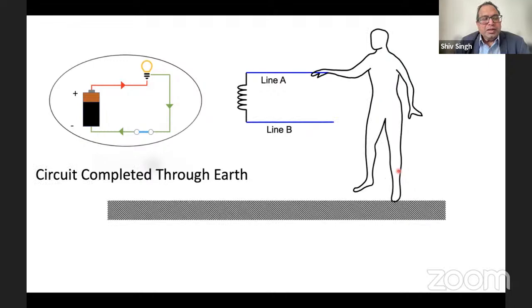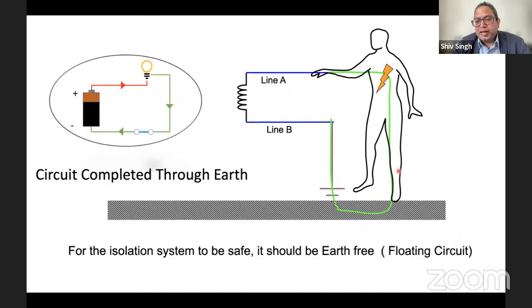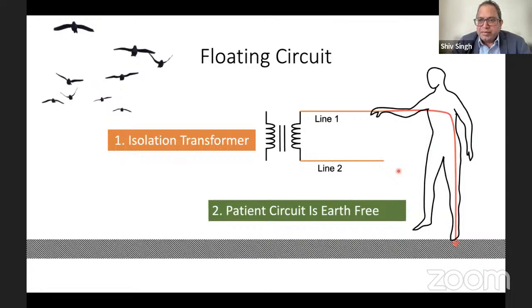Like I said, if by mistake, or because somebody tried to act very clever, line two is also earthed accidentally, then this is no longer isolated. For a supply to be isolated, it needs to be isolated from the earth. That's the definition of isolation. For an isolation system to be safe, it should be earth-free. This is also what we call a floating circuit, where there is no earth. A floating circuit requires two things. One, it uses an isolation transformer. And second, the patient circuit is always earth-free. Now, you cannot float if you're on the earth, can you? Well, you can't fly, actually.